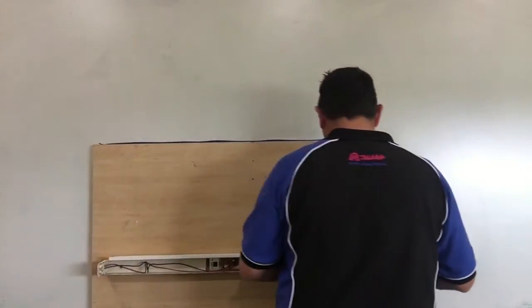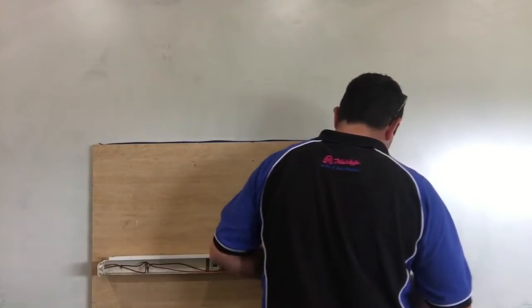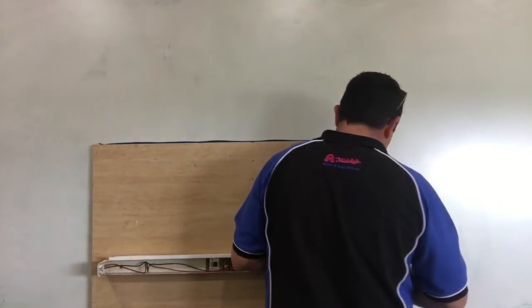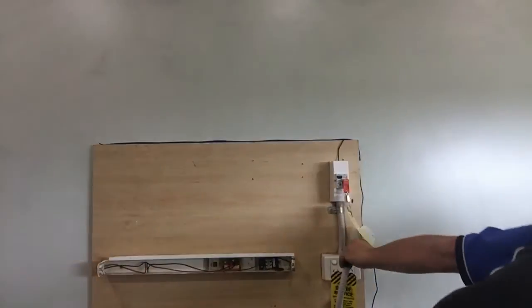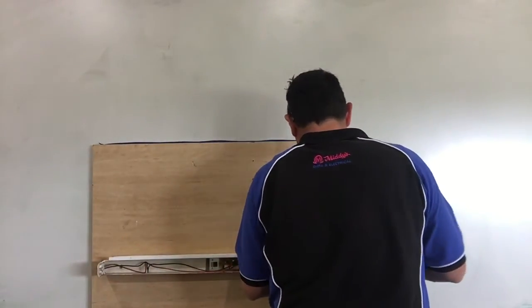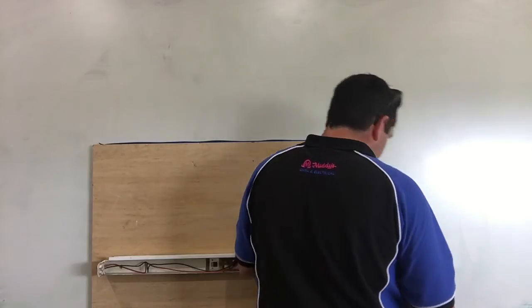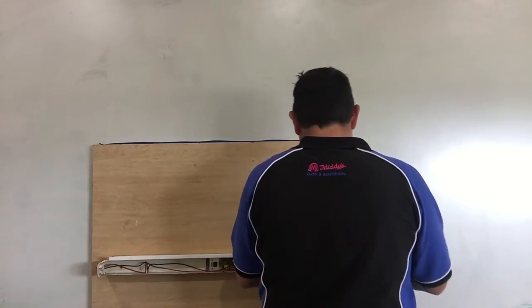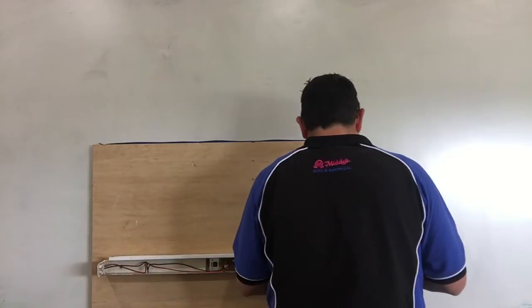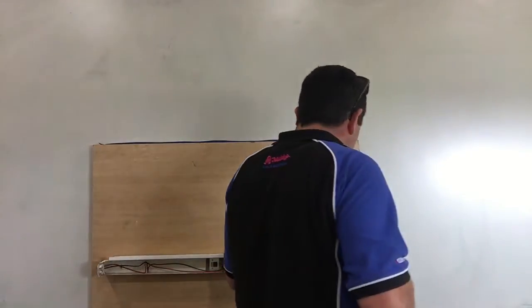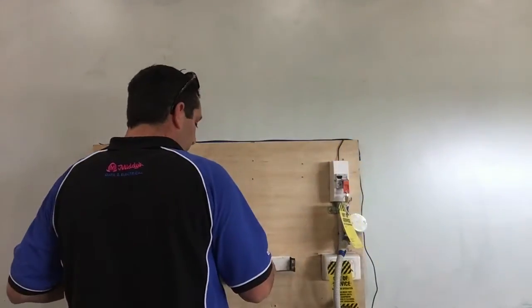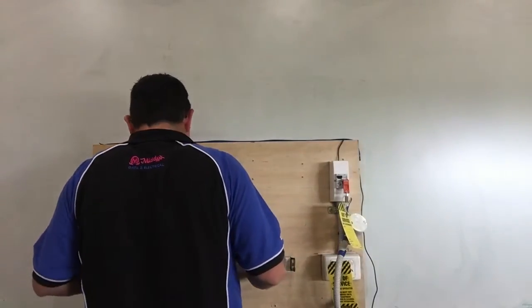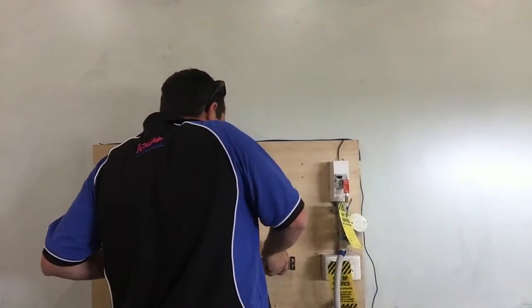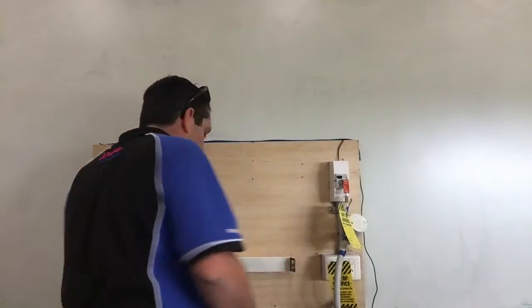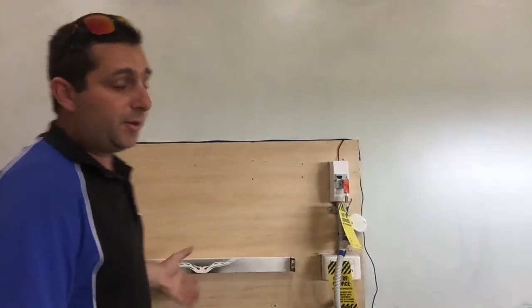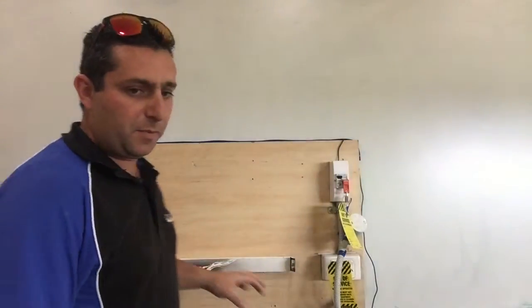And this should be secured somewhere out of the way with a cable tie or something of the like, just to help give it that little bit of extra mechanical protection. We don't want to have this floating around somewhere that it can be getting damaged. Put your cover back on, because you don't want that getting lost. You may need it if this appliance gets repaired rather than replaced. We don't want to be searching around for screws and that type of thing.